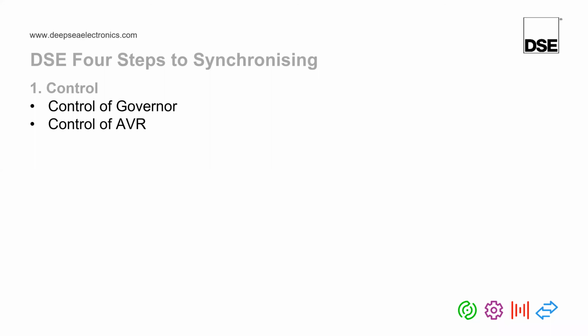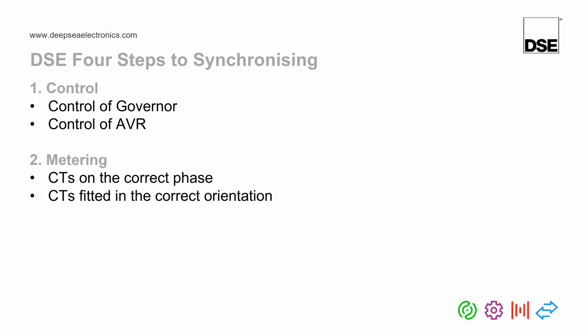The first of the 4 steps is what we call control, basically making sure that the DeepSea module has good control over the governor and AVR. The second step is to make sure that the DeepSea module is correctly monitoring the current that the generator produces, basically making sure power readings, things like that, are all correct.